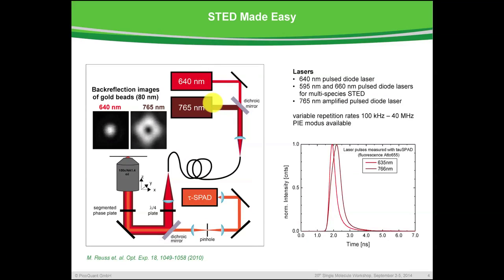We have, as excitation laser, the 640 nanometer, and a STED laser — a high-power 765 nanometer laser. These two are overlaid and fiber-coupled, and the output of the fiber goes into the main optical unit of our microscope. Inside the microscope, the two lasers take exactly the same beam path. The output of the fiber is linearly polarized; we need a quarter-wave plate to have circular polarization. The lasers are reflected by a dichroic mirror and then passed into the sample, focused with a high numerical aperture objective. The donut is created with a very special segmented phase plate, which leaves the excitation laser unaffected.